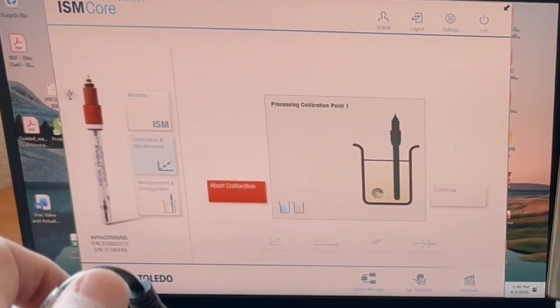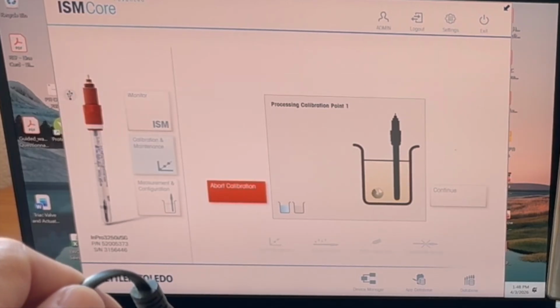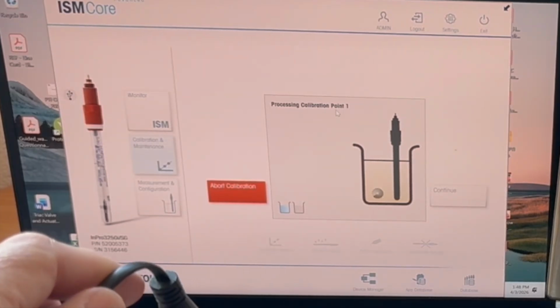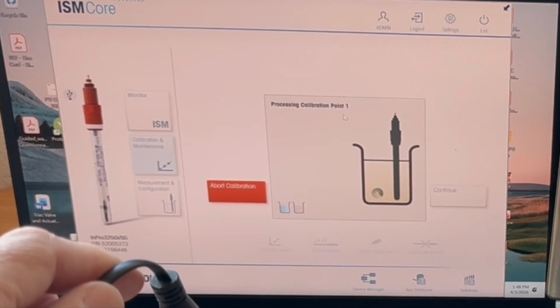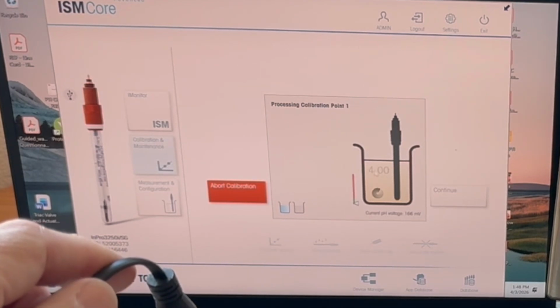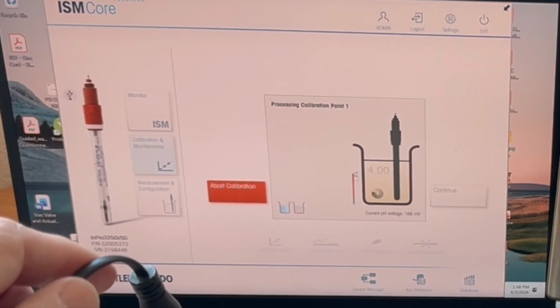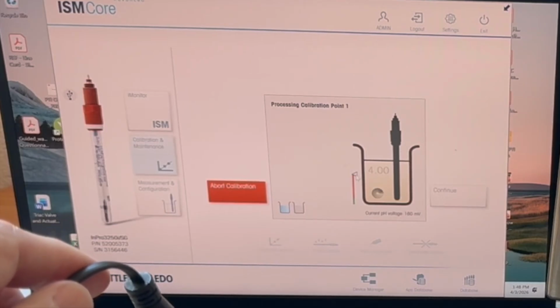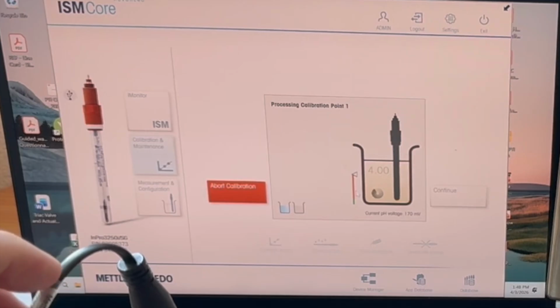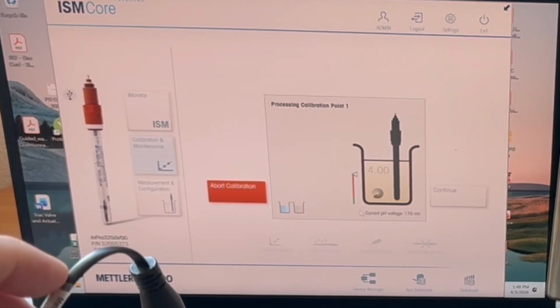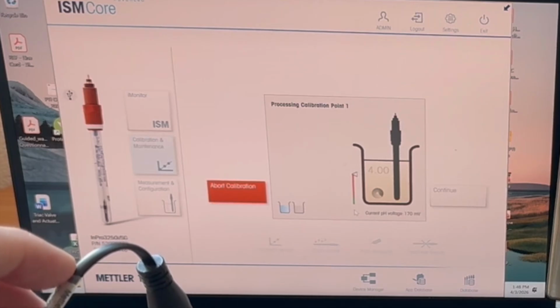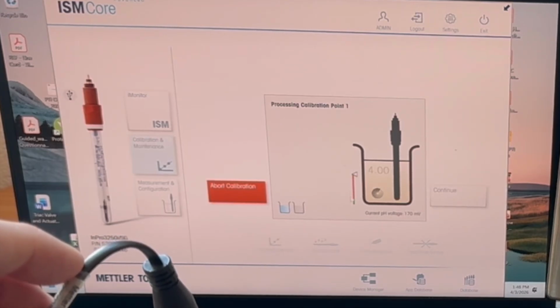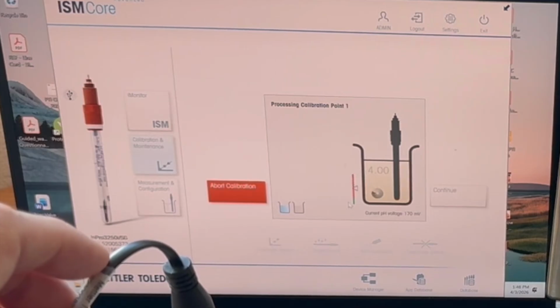We've got a wheel indicating that it's trying to figure out what the sensor is sitting in, because it didn't tell me to put it into buffer 4, 7, or 10. It will recognize from the millivolts that in this case it's buffer 4. And then we have a sort of a stability indicator that's built into this. So this little shape here is actually going to move down in terms of the rate of change over time. It's looking for a stable, minimal rate of change over time before that will lock in. So we just have to wait for that for a few seconds. And you can see how it's rapidly dialing in, getting to a more stable reading, probably.